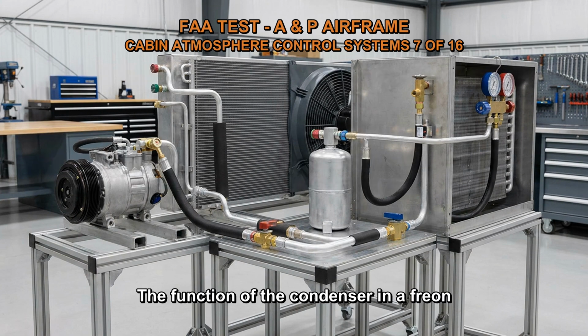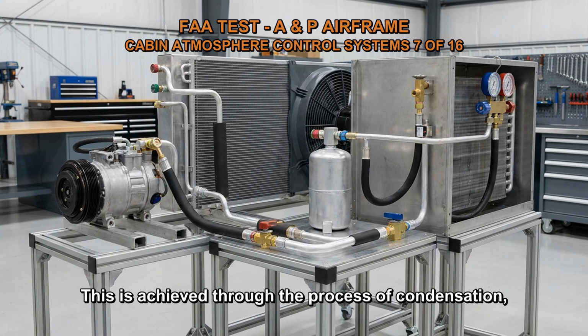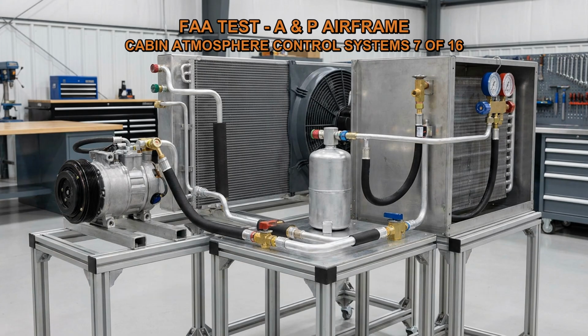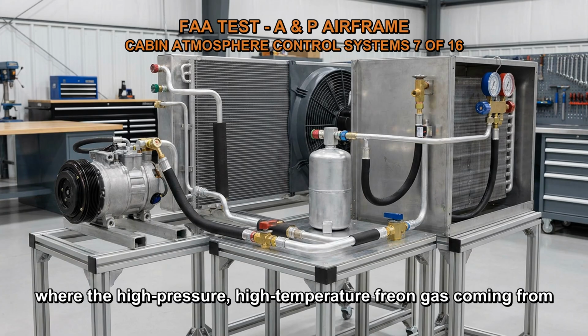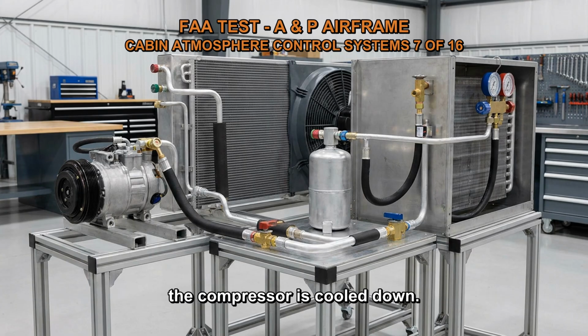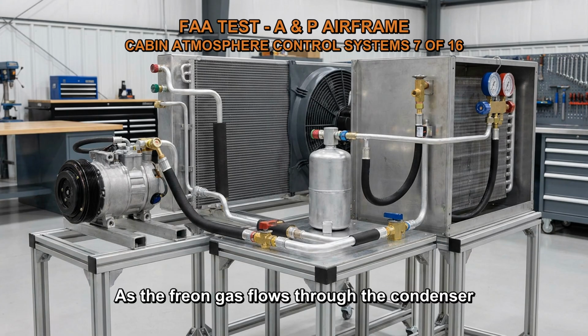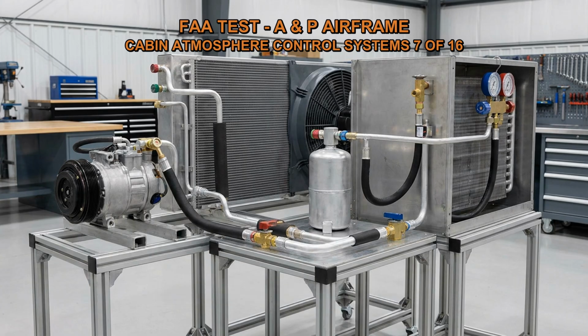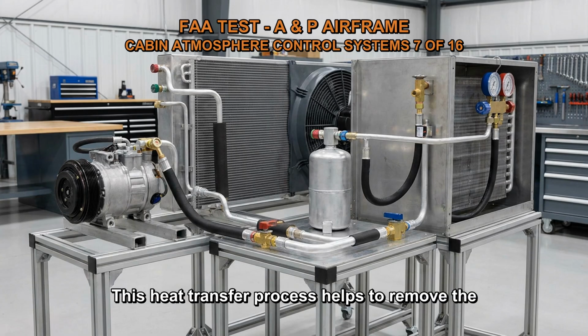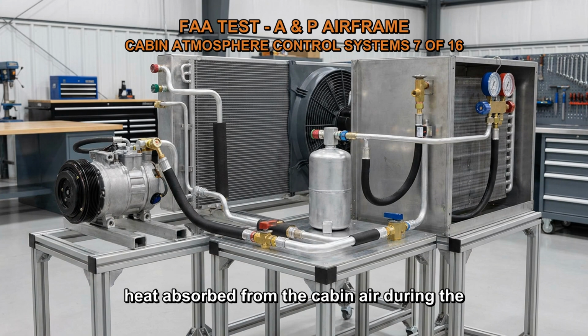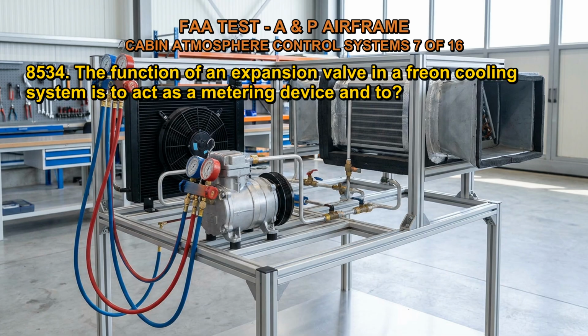The function of the condenser in a Freon cooling system is to transfer heat from the Freon gas to ambient air. This is achieved through the process of condensation, where the high-pressure, high-temperature Freon gas coming from the compressor is cooled down. As the Freon gas flows through the condenser coils, ambient air is blown over the coils, causing the gas to release heat and convert into a high-pressure liquid. This heat transfer process helps to remove the heat absorbed from the cabin air during the cooling cycle.